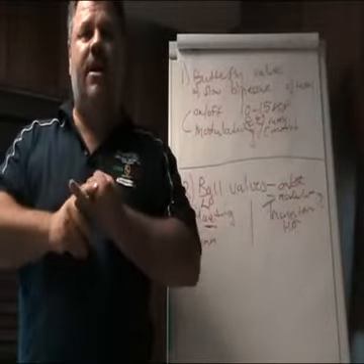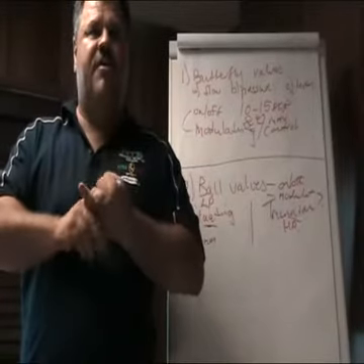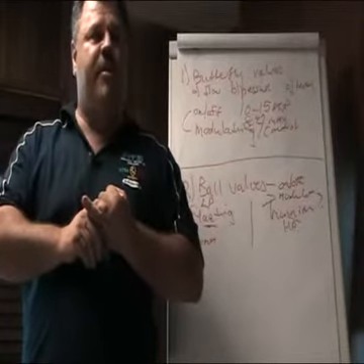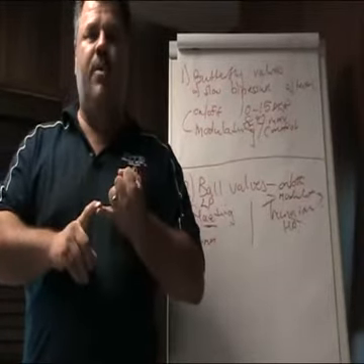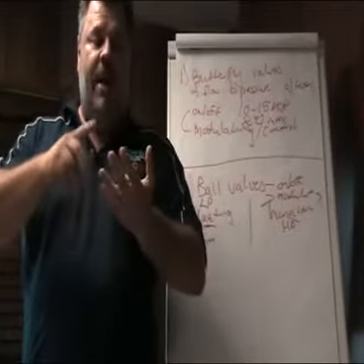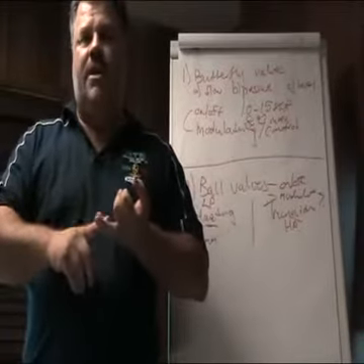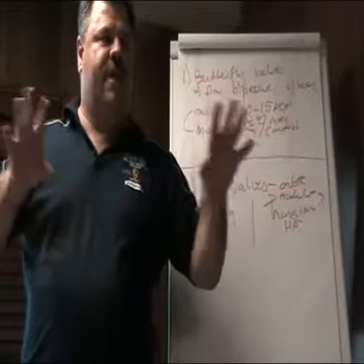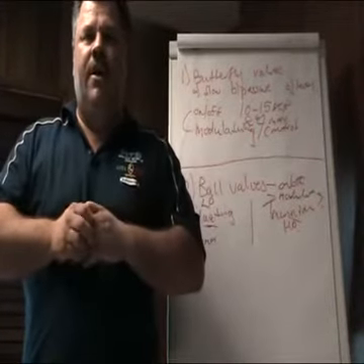Alright, can we step off ball valves for now? Remember, you can get different materials. Carbon steel and stainless steel are the most common types of materials you get worldwide on ball valves. A lot of people, when they stock ball valves, they stock carbon steel, which is called WCB or A105, depending on which code, and then stainless steel, whether it's 316L, 304, or CF8M, but the bottom line, those are the two types. They will have, say, 100 carbon steel and 50 stainless steel. Correct, because it's cheaper for us, because you guys don't buy a lot. That's the reason.